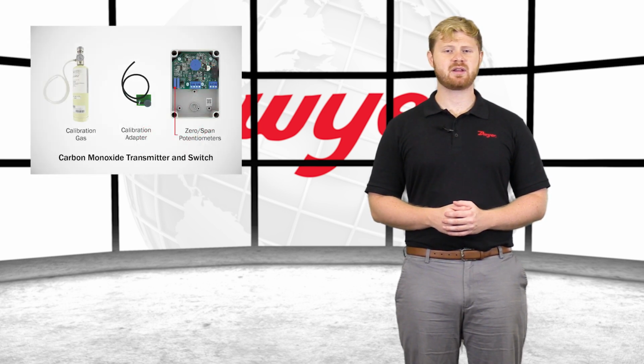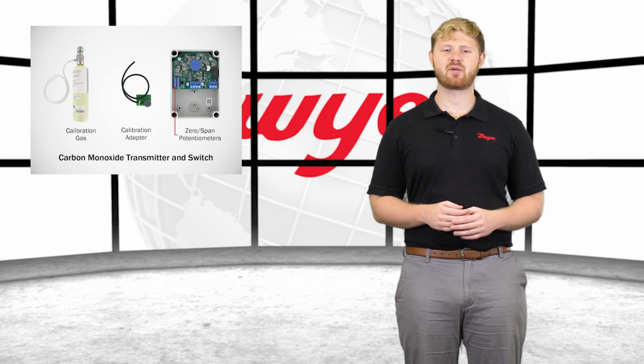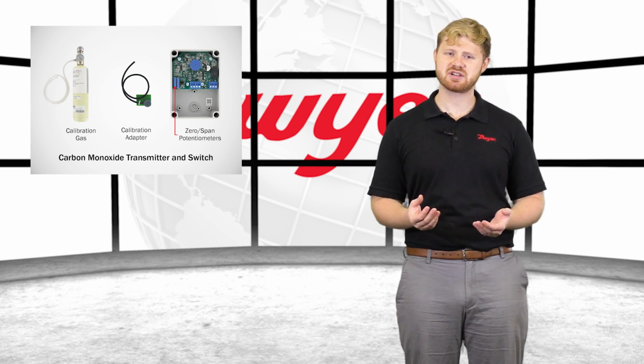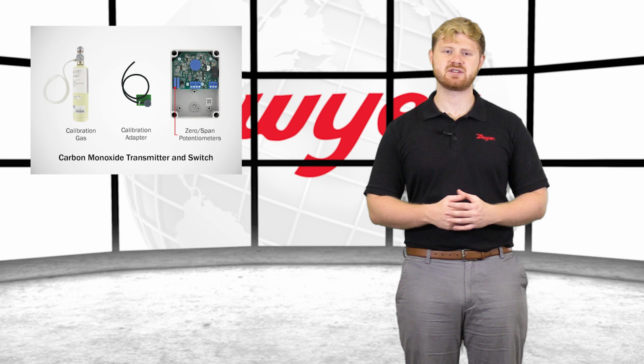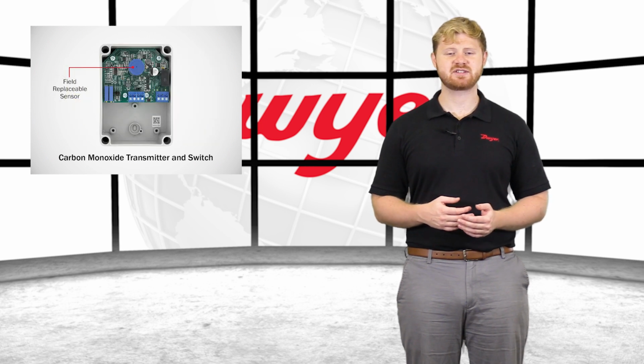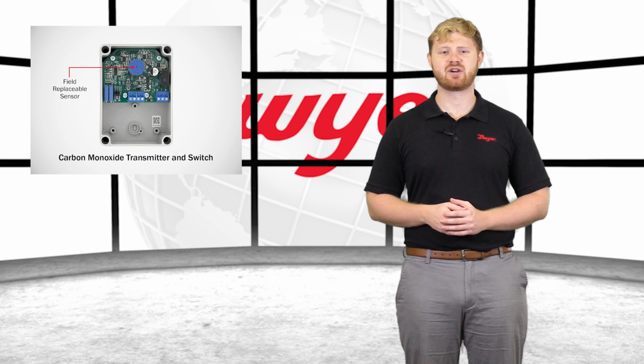Field calibration can be completed using calibration gas and calibration adapter accessories in combination with the onboard zero and span potentiometers. In the event of the sensor needing to be replaced, Dwyer offers a field replaceable sensor, minimizing costs.